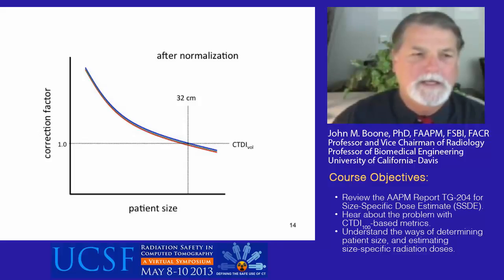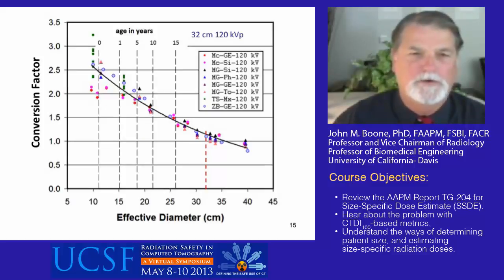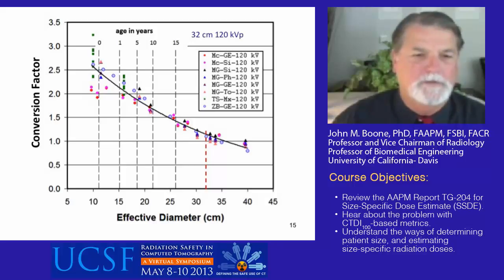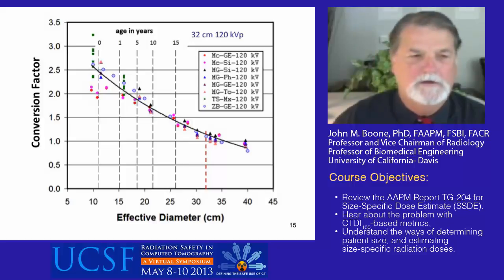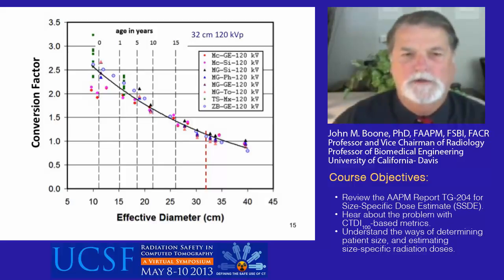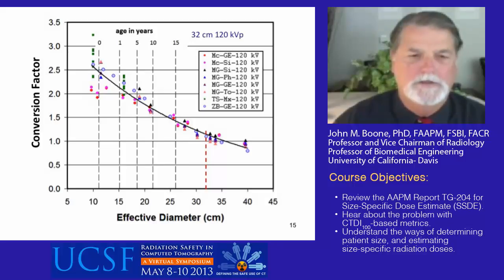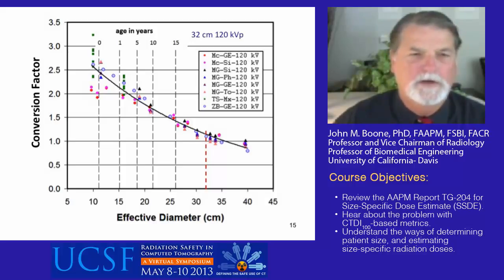When the data from all groups are combined at 120 KV for the 32-centimeter diameter phantom, it's a pretty good fit. The vertical red dashed line at about 32 centimeters would be expected to have a conversion factor of unity, but it's slightly higher because this correction implies a conversion from air KERMA — what CT-CTDI vol is measured in — to tissue dose in milligray. That's why the best-fit line is slightly elevated above unity at 32 centimeters.